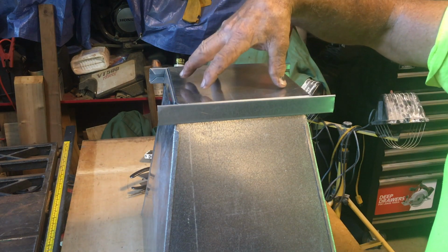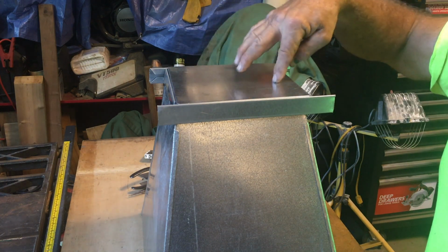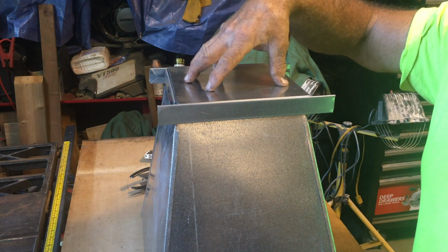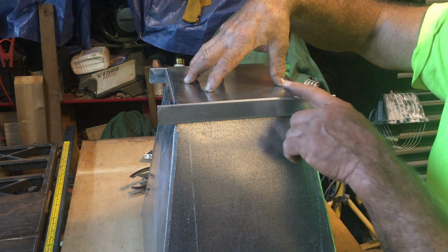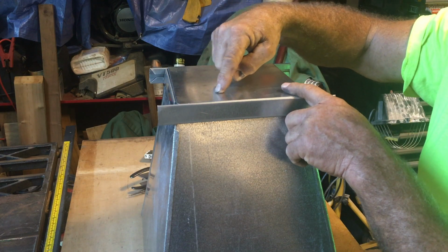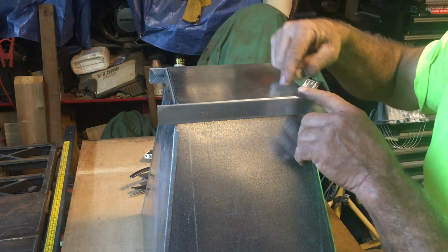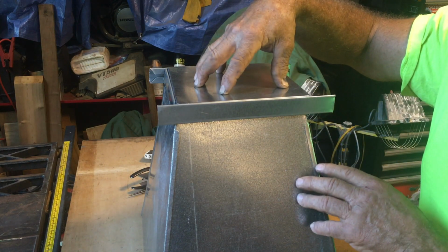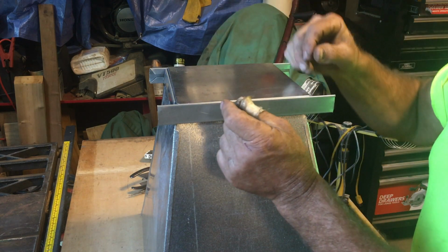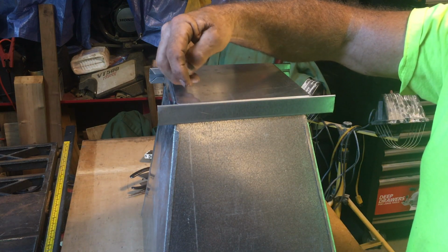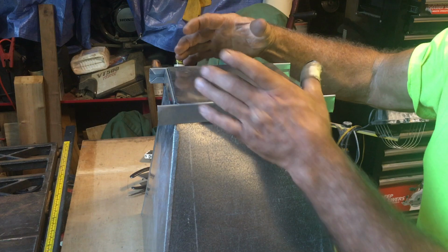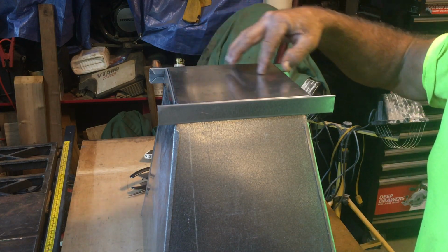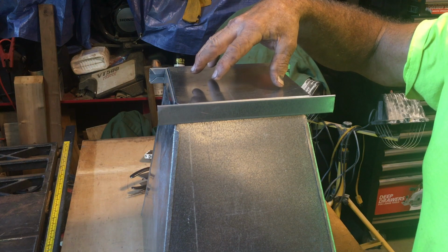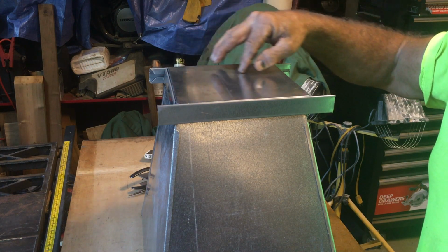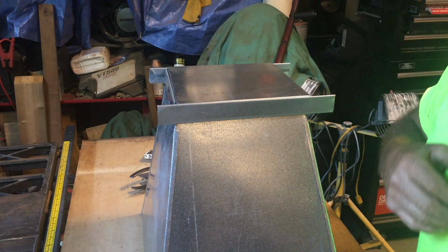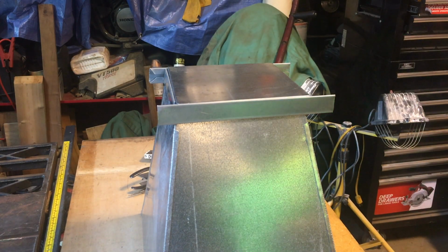All I've got to do now is get the fan assembly and cut the diameter of the hole where that fan will insert down inside. Once I cut the hole, I'll cut a tab on the 4 corners out of that plug, bend the tab up, and use some little 3/8 inch long tek screws to screw into the fan to hold everything in place. I'm going to cut it as tight as possible - it's probably not going to leak much, but if it does you could put a dab of caulk around, though that seldom happens. It's usually pretty doggone tight.